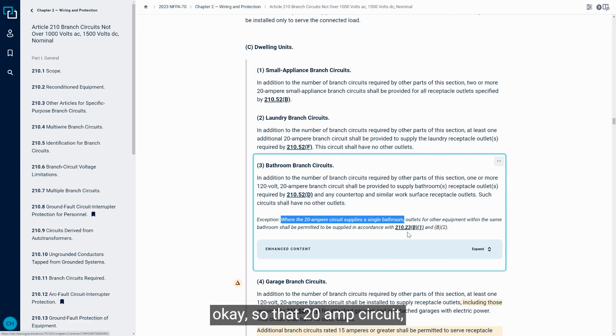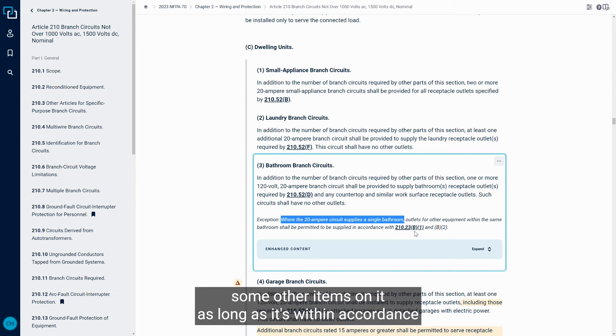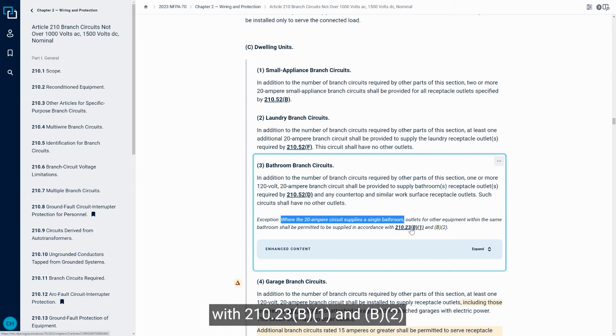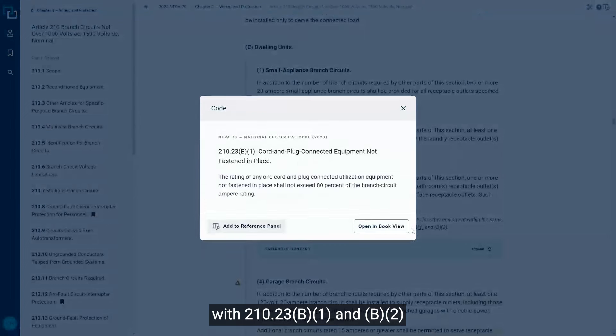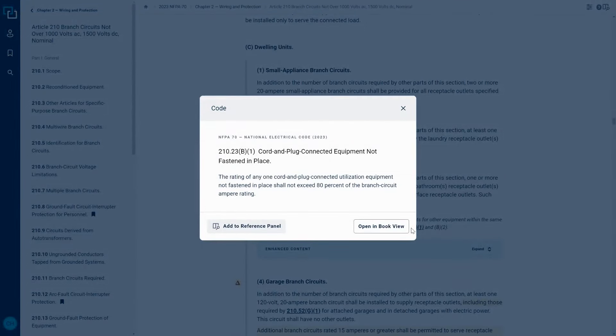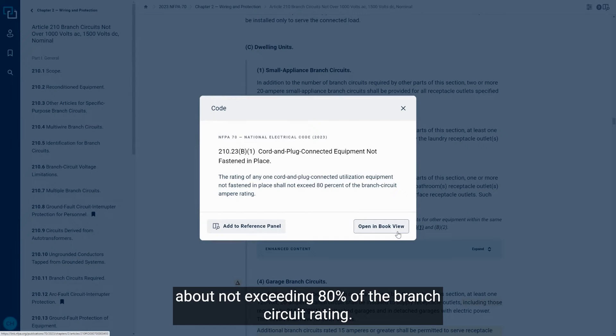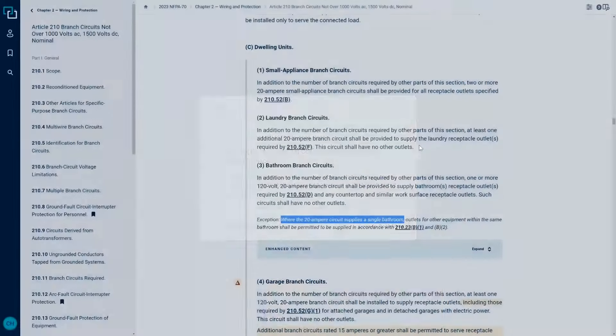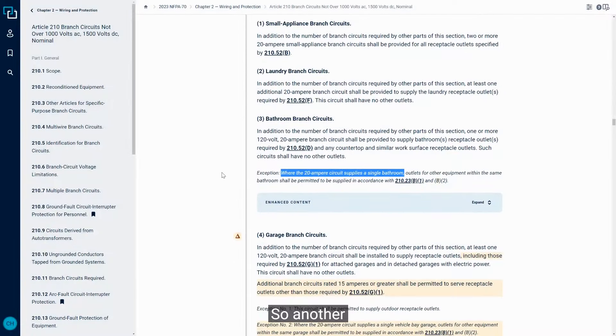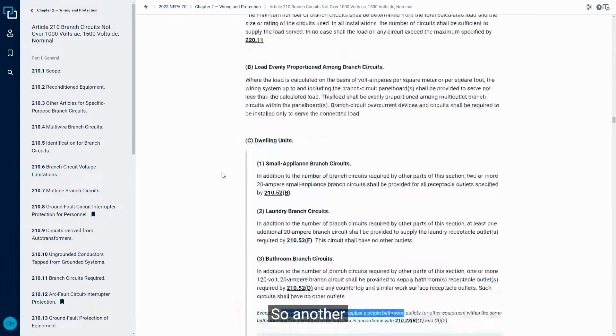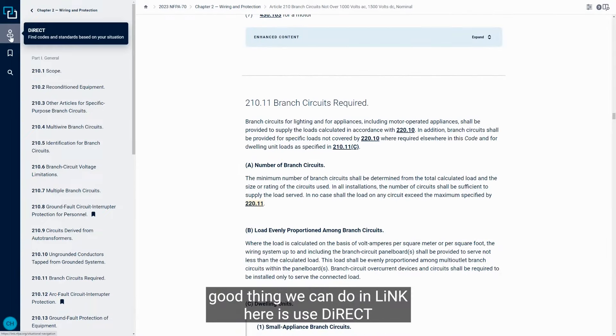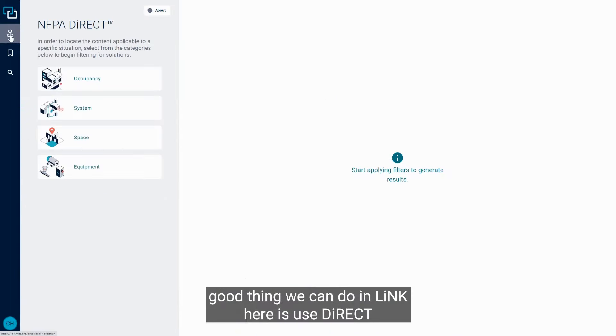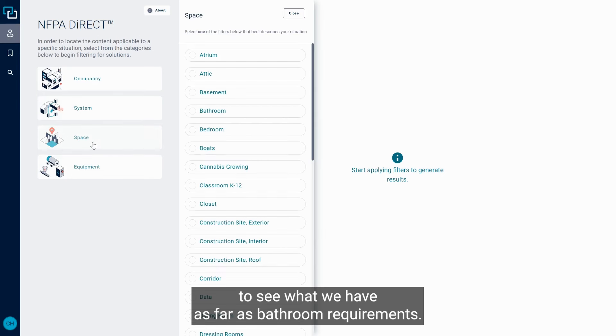Okay, so that 20 amp circuit, if it's just feeding one single bathroom, you have some options to install some other items on it, as long as it's within accordance with 210.23.B.1 and B.2. So B.1 gives you some information about not exceeding 80% of the branch circuit rating.